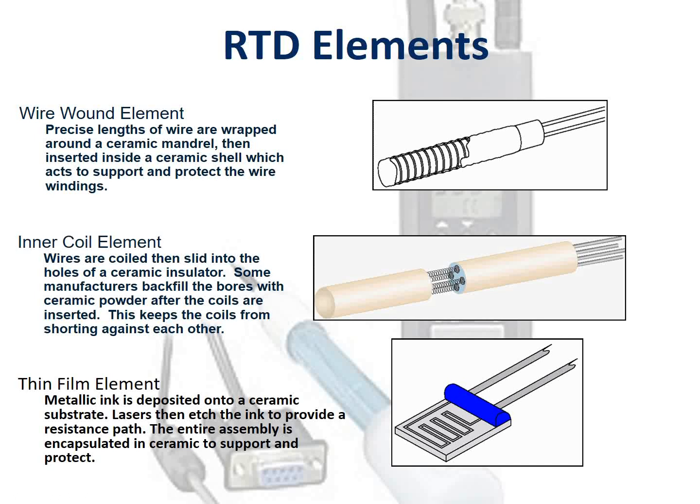There are three types of RTD constructions. In the wire wound element RTD, precise lengths of wire are wrapped around a ceramic mandrel, then inserted inside a ceramic shell which acts to support and protect the wire windings.